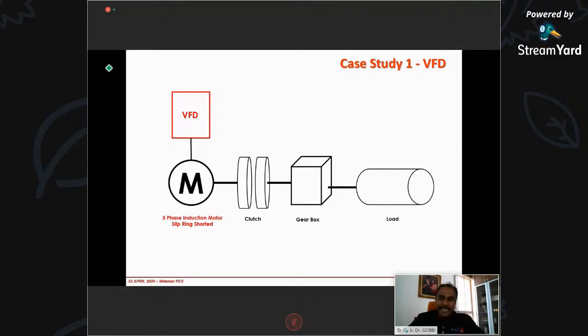And what they did, they actually set the frequency to 48 hertz. Remember, this is a more than 200 kilowatt motor. That means the VFD was about 500 horsepower. Okay, 500, huge, very huge. That means they spent a lot of money and they had to place the VFD in a special room with air conditioning.